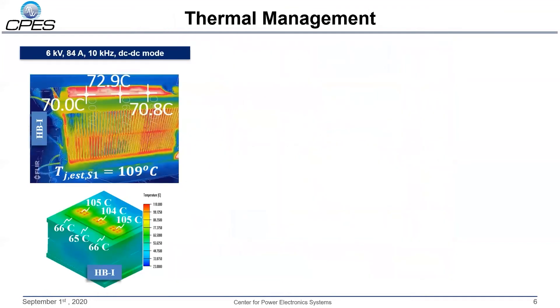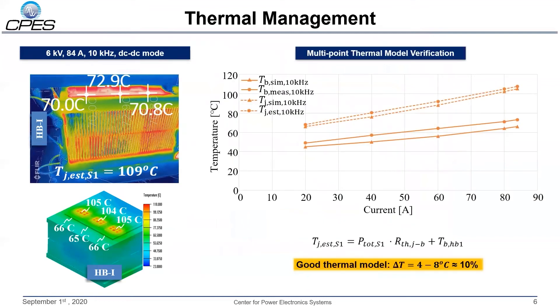The fifth step takes place after the power cell's steady state temperature is reached. Temperature management is assessed with a base plate temperature of 73 degrees Celsius. The simulation model shows generally lower base plate temperatures than the experimentally measured ones, with differences of 4 to 8 degrees Celsius. Comparing junction temperature between the two shows a similar discrepancy of around 5 degrees. Base plate and junction temperatures have been compared at multiple points to the measured ones. The model shows the same trends as the measured and estimated values with a maximum difference of 8 degrees Celsius, which is acceptable considering the complexity of the system and its cooling. From a practical standpoint, having a thermal model that is 90% accurate is extremely valuable due to the difficulty in developing extremely accurate models in all possible scenarios. This inaccuracy should be carefully considered when assessing the developed SOA.